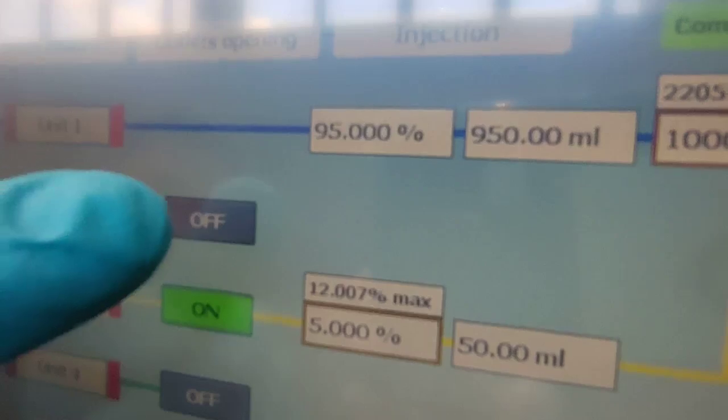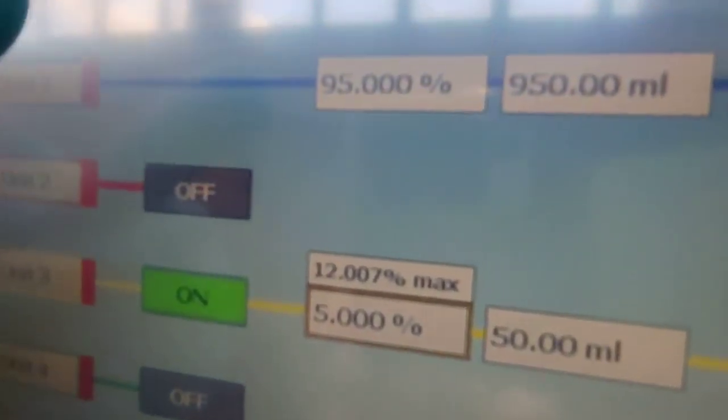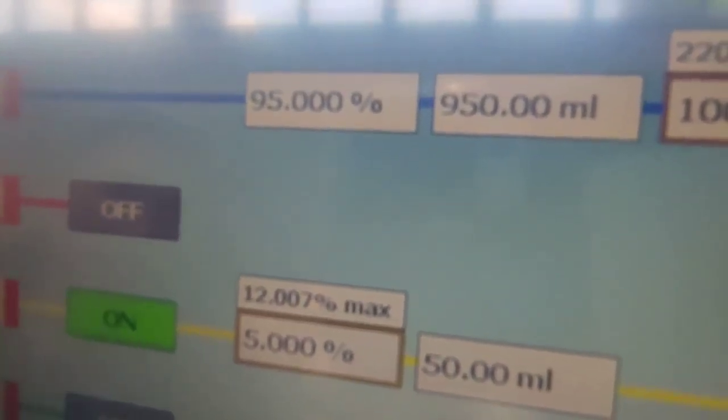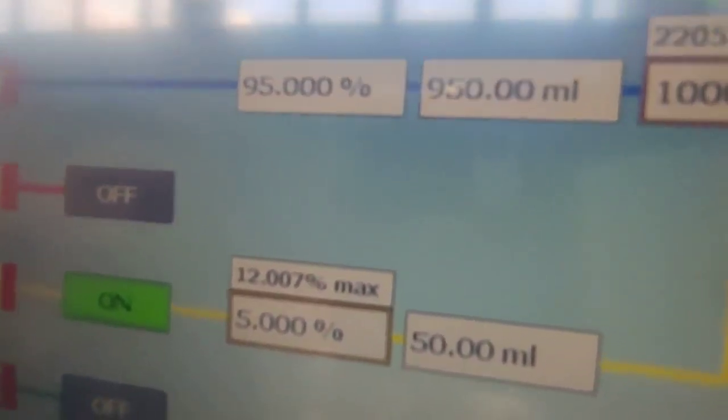As the additive unit percentage is set to five percent, the main dosing unit is going to dose 95 percent which corresponds to 950 ml, while the additive unit doses 50 ml.